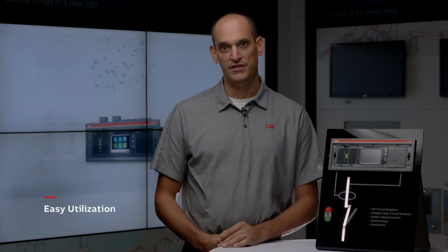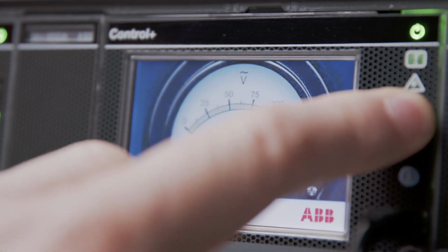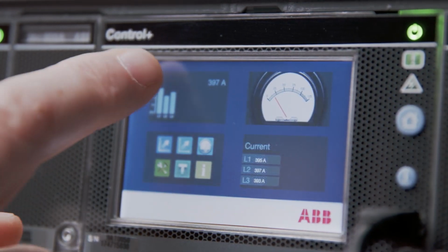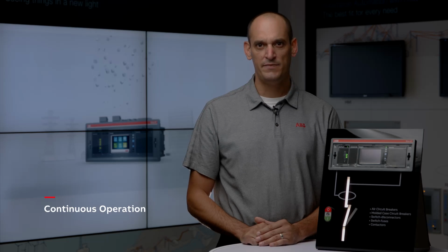Ekip UP offers many advantages for monitoring and analyzing power quality. One, it's easy to use and to upgrade existing plants with open sensors to maximize uptime and reduce impacts on existing switchgear. A touchscreen display and Ekip Connect software tool designed with user-friendly interface makes Ekip UP a simple yet powerful tool. Two, it operates continuously, detecting power quality issues with the capability to monitor up to the 50th harmonic, to see real-time waveforms, to configure alarm events, and two buffers of data logger to record waveforms for event diagnosis.